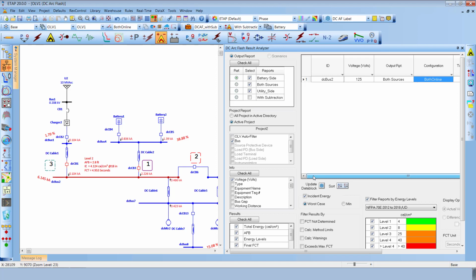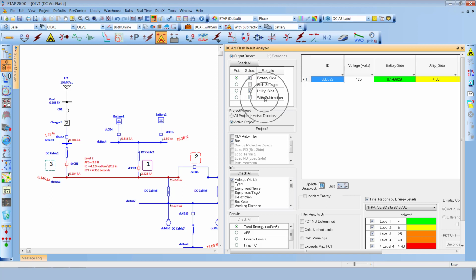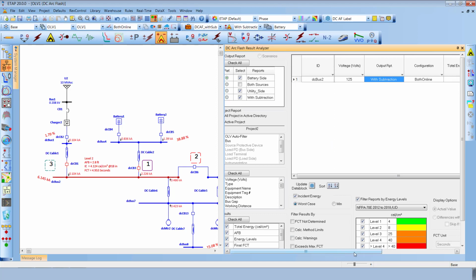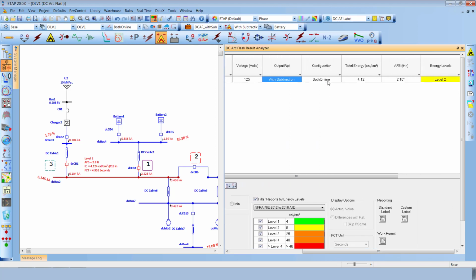Whereas, depending upon the logical implementation of the subtraction method, it is possible to eliminate that particular report, considering the fact that each source gets de-energized after the corresponding fault clearing time is calculated from the de-energizing source protective device. We can compare the three different scenarios with the subtraction and then determine the incident energy calculation with the subtraction mode on and consider which gives the worst case scenario.